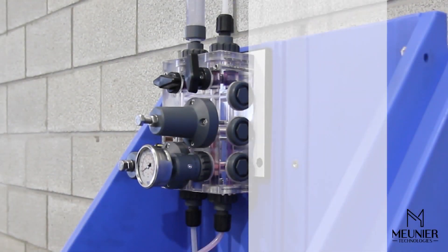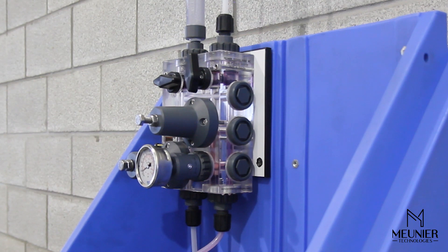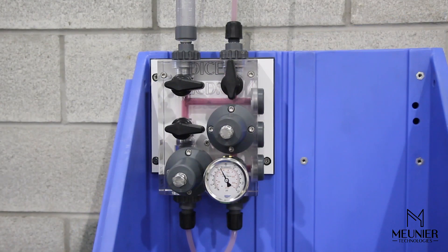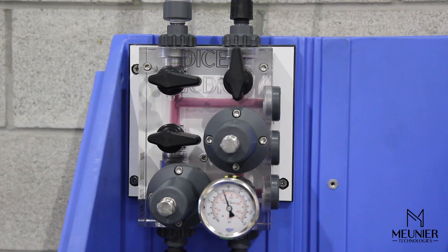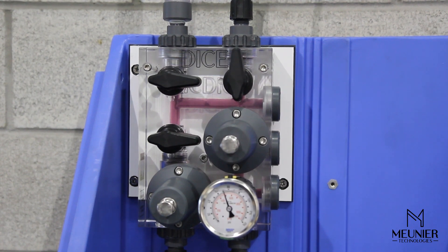In normal operation, the dosing pump will be pumping chemicals from the chemical tank into the DICE inlet, then passing through the back pressure valve and into the injection line feeding the process. The pressure indicator will be measuring the back pressure valve set point, in this case 70 psi. When a clear acrylic module is used, fluid flow through the module can be seen by looking through the transparent material, making it extremely easy to troubleshoot the system.